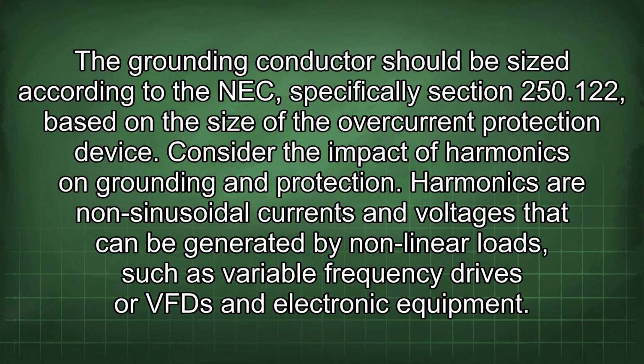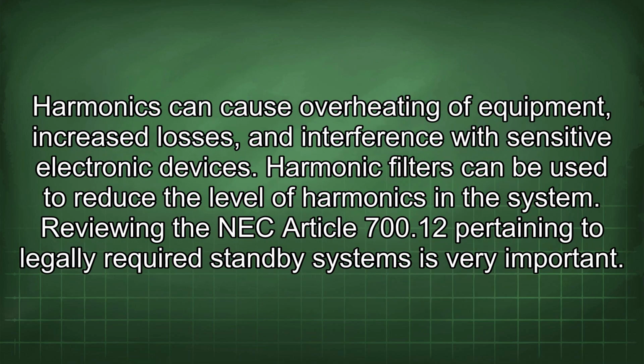Consider the impact of harmonics on grounding and protection. Harmonics are non-sinusoidal currents and voltages that can be generated by nonlinear loads such as variable frequency drives, or VFDs, and electronic equipment. Harmonics can cause overheating of equipment, increased losses, and interference with sensitive electronic devices. Harmonic filters can be used to reduce the level of harmonics in the system.